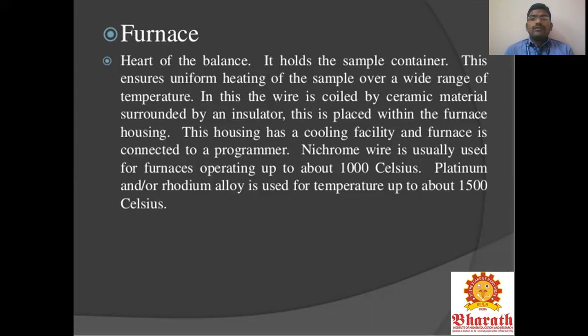In this, the wire is coiled on a ceramic material surrounded by an insulator. This is placed within the furnace housing. The furnace has cooling facilities and is connected to the programmer. Nichrome wire is usually used for furnaces operating up to 1000 degrees Celsius. A platinum and rhodium alloy is used for temperatures up to about 1500 degrees Celsius. Nichrome wire is used for about 1000 degrees Celsius.